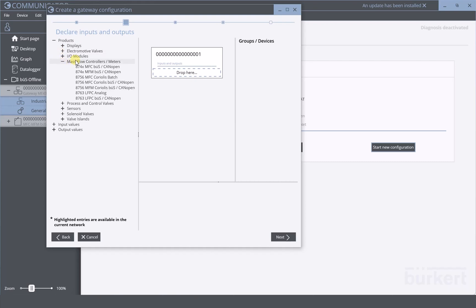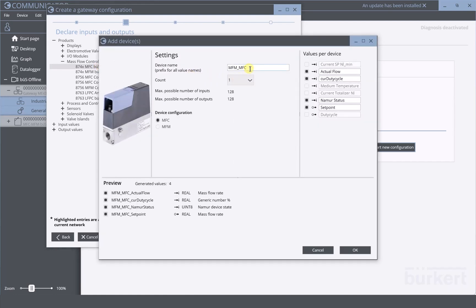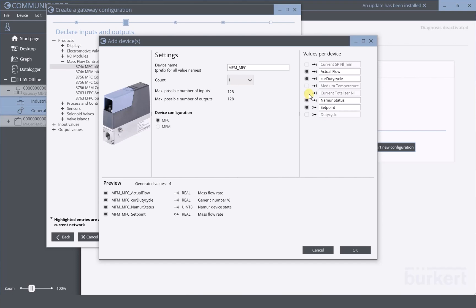The main step of this configuration is to declare the input and output variables which will be exchanged with the PLC. To make this simpler, we've created a product catalog for you. Under the category mass flow controllers, you can find the right type of device. By simply dragging and dropping it, a pop-up window appears where you can see and change the device name, change the count of devices, and add or remove the process values you want to transmit to the PLC. The actual flow, the current duty cycle, the Namur status, and the set point are pre-selected values. If you wish to add the medium temperature, you can simply select or remove it here.